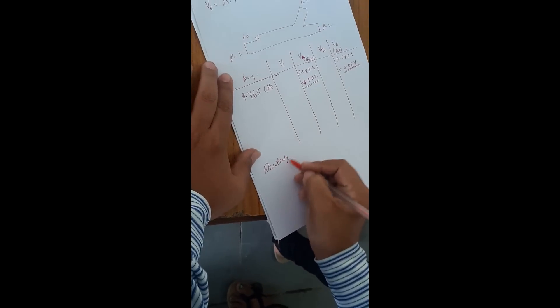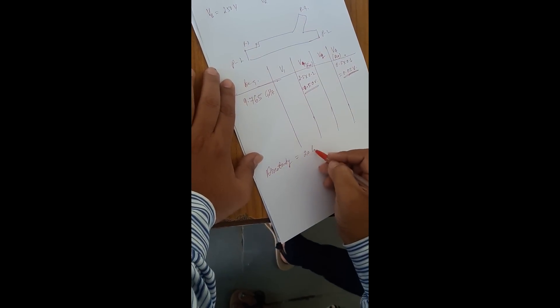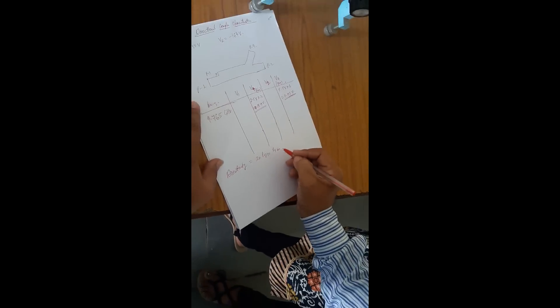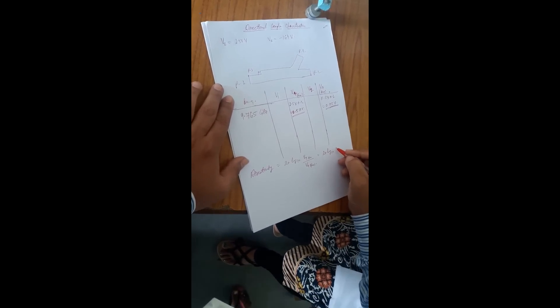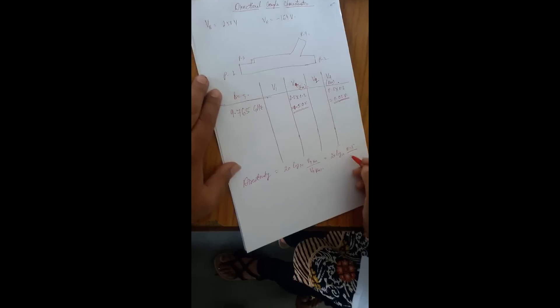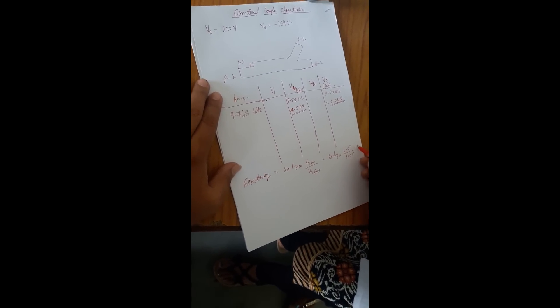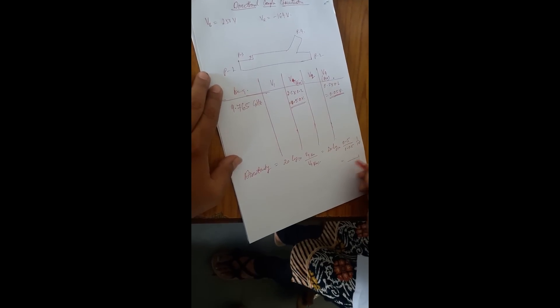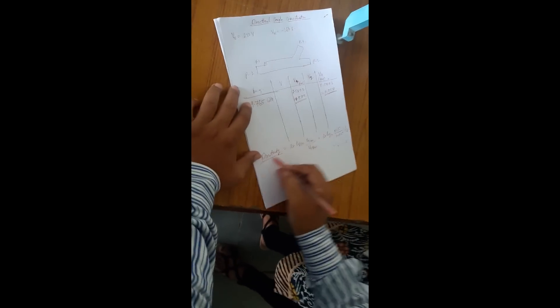This is the voltage we are getting in the reverse direction. So we can calculate the directivity. Directivity will be 20 log10 of V in the forward direction divided by V in the reverse direction. This is one calculation of your directivity.